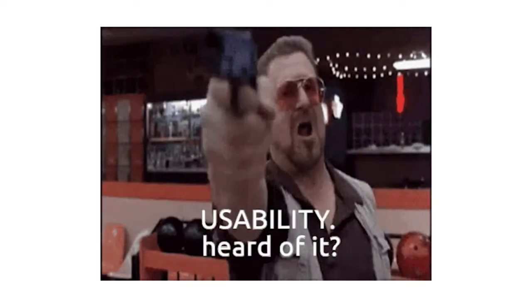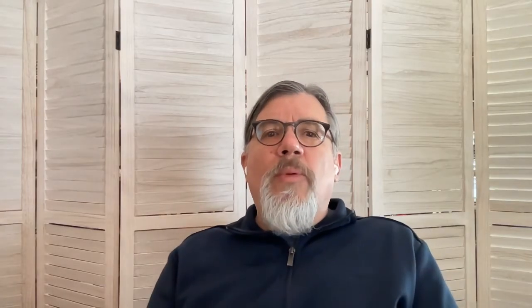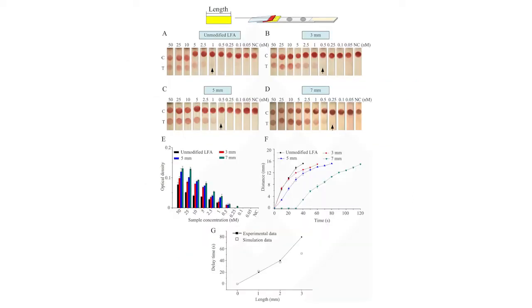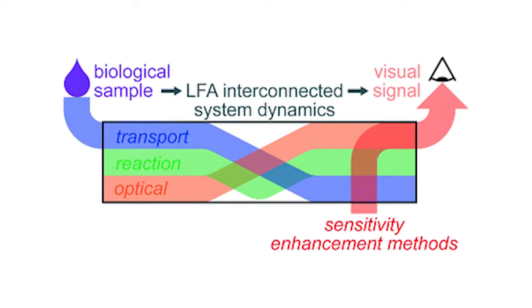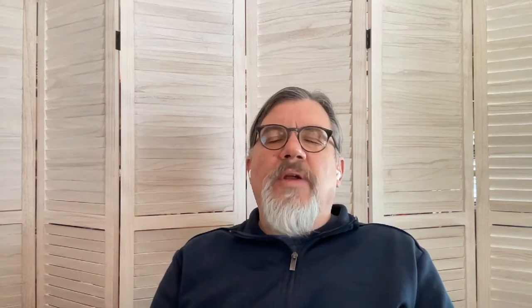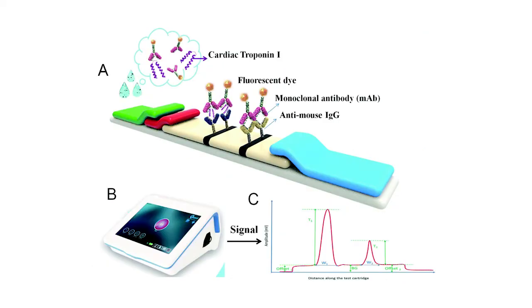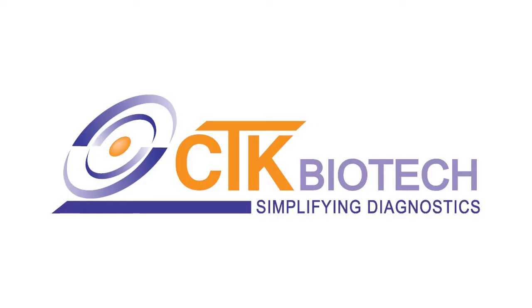The areas of innovation are two: one is trying to improve the performance of the tests, and the second is trying to improve the usability. To improve performance, typically people want to improve the sensitivity or lower limit of detection. They have tried to do that by increasing the signal of the test. The color of gold is only visible at a fairly high concentration, so people have moved to fluorescent dyes. But you can't see fluorescent dyes directly, so you need to use a reader, as opposed to the colorimetric version where you simply look at it and know whether it's reactive or not.